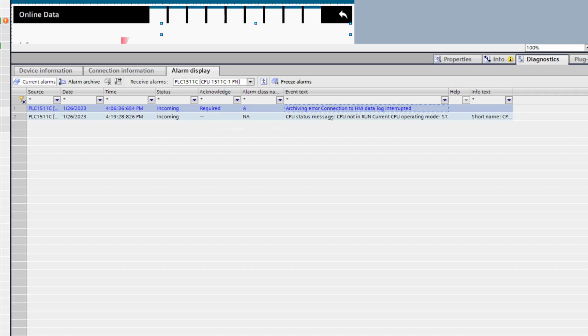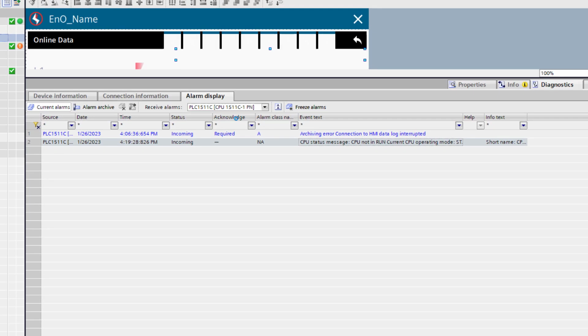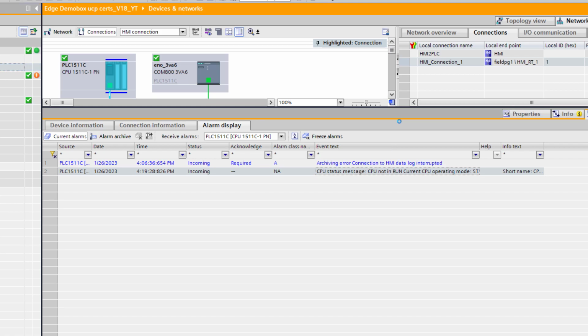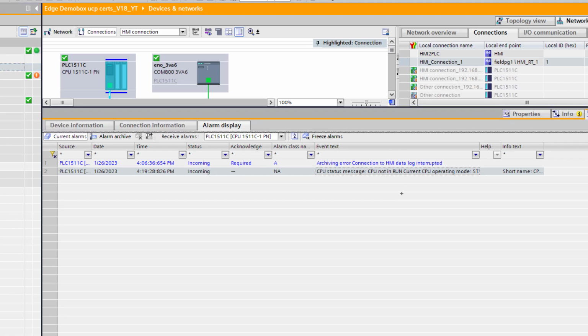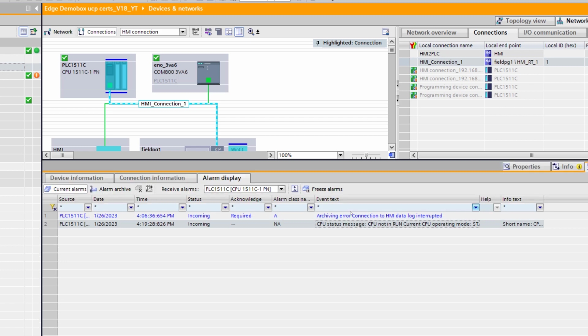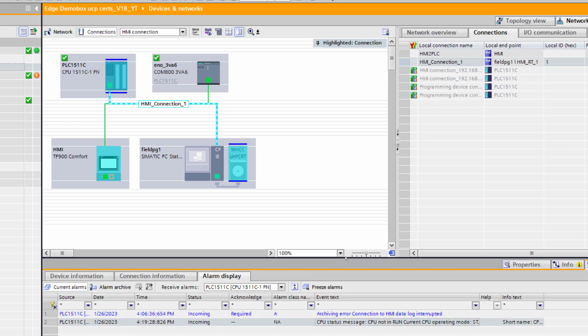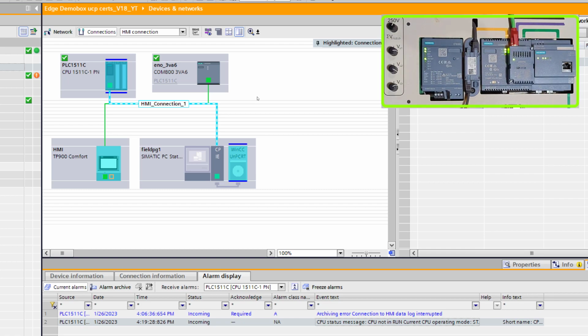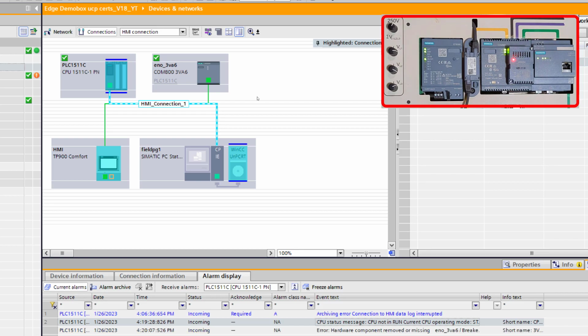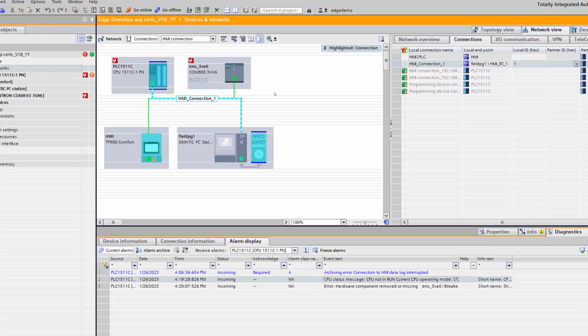A unique feature of the Profinet along with the S7-1500 PLC is that despite the PLC being in stop mode, we can still scan the network and the components to determine their diagnostics. So for example, even though the PLC is in stop, the COM800 module here is still reporting its statuses. Removing any of the cabling all the way down to the breaker also produces similar errors. So if I unplug the Profinet cable from the COM800, pretty quickly you'll see it'll generate an alarm indicating that the component was removed or missing.